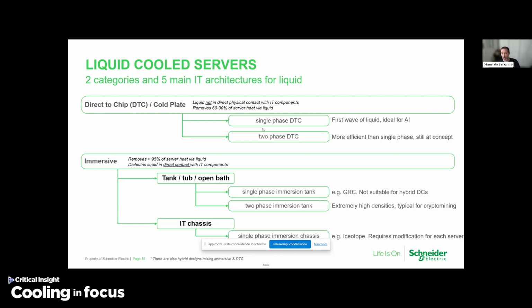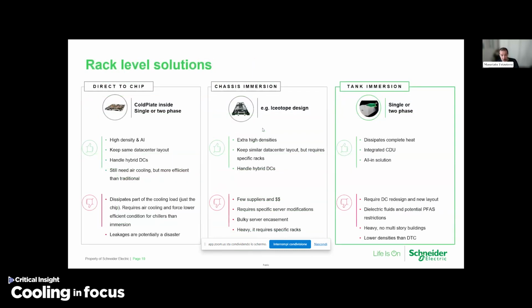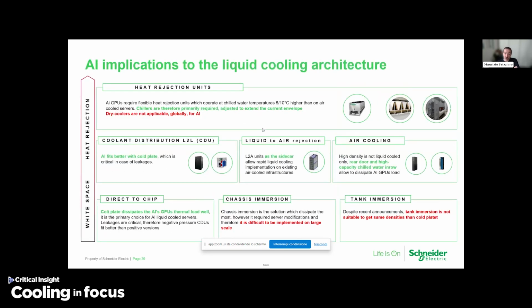These all have pros and cons by application. It's true that the first wave of liquid cooling is single-phase direct chip because it's easy to implement, it does not reinvent the wheel or the data center layout, but all the others have pros and cons. So the recommendation, and it's not possible to cover in 20 minutes, is to be in contact with the players in the game and define together the best solution on the white space side, but also on the heat rejection or distribution side.